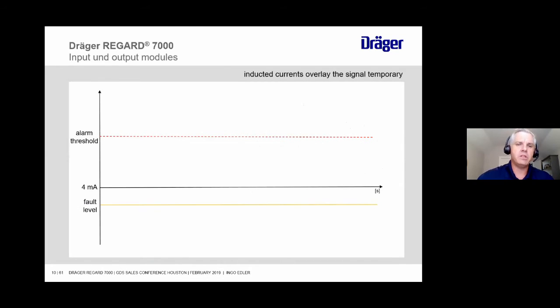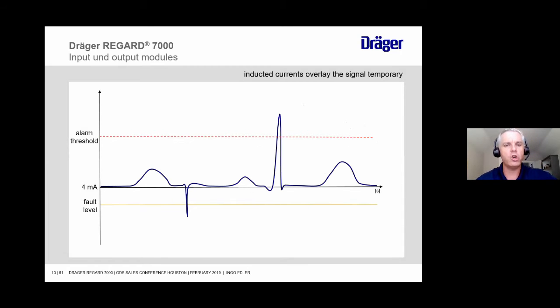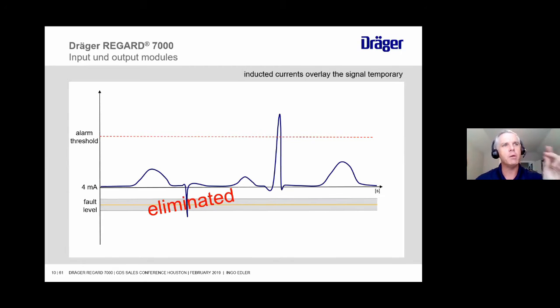So this is a little graph of what gas detection could look like if you plotted the milliamp values changing over time. Your first little hump there, that could be gas detection. That first spiky thing down, that's probably a fault of some kind. That little small incline is gas detection. That big spiky thing, that's probably not gas. For that first little spiky thing down, we put a little tolerance around that special signal because it has fallen below 4 milliamps. So we'll say 2 milliamps plus or minus 10%. So 2 milliamps to 2.2 or 1.8, we're going to make sure that we're tripping that fault.